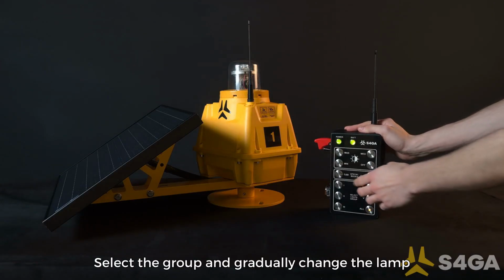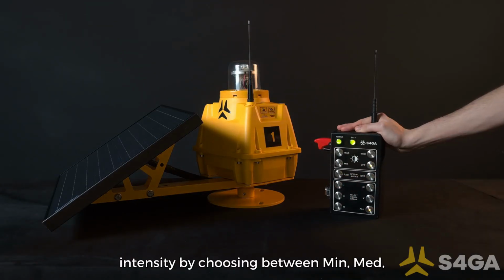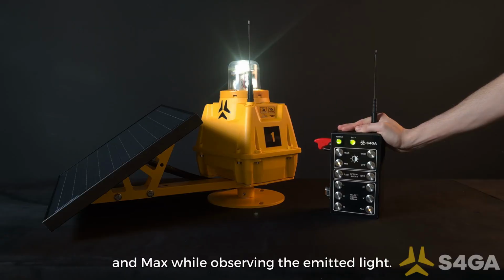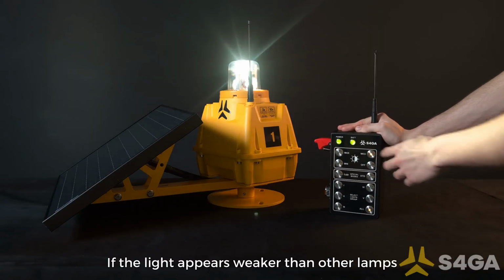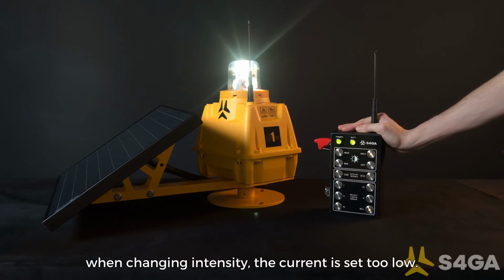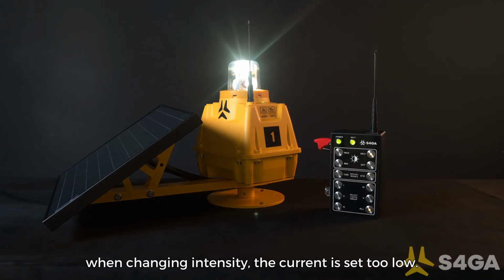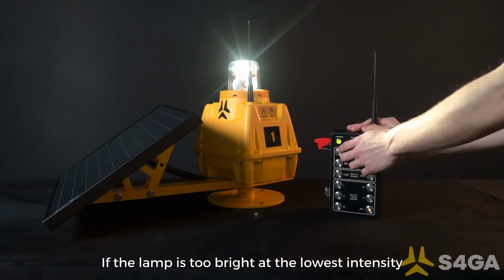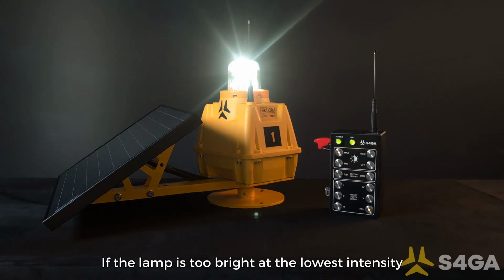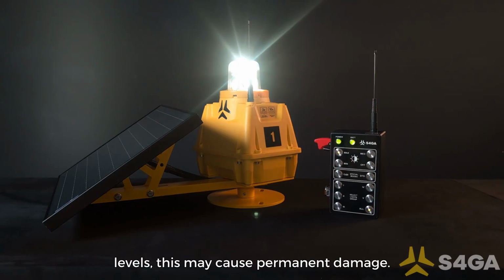Select the group and gradually change the lamp intensity by choosing between minimum, medium, and maximum while observing the emitted light. If the light appears weaker than other lamps when changing intensity, the current is set too low. If the lamp is too bright at the lowest intensity levels, this may cause permanent damage. In these situations, reconfigure the current.